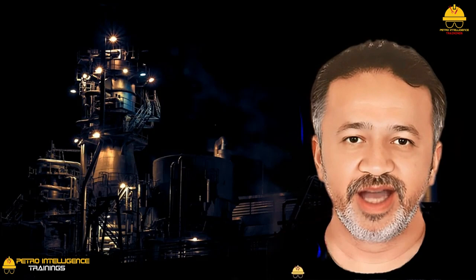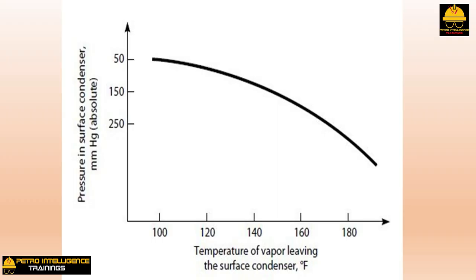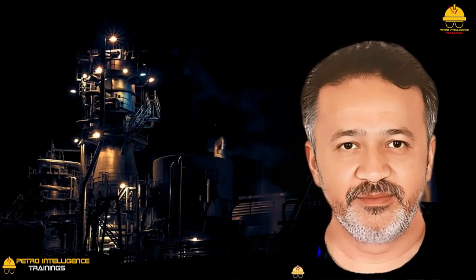Even without loss of vacuum due to an air leak, surface condenser performance is degraded as the concentration of non-condensables increases inside the condenser. While shell-side fouling in a surface condenser is uncommon, loss of heat transfer coefficient due to air binding is as common as tube-side fouling due to poor quality cooling water. Jet problems include too high or too low motive steam pressure, excess wear on steam nozzles, high condenser back pressure, and air leaks exceeding jet capacity.